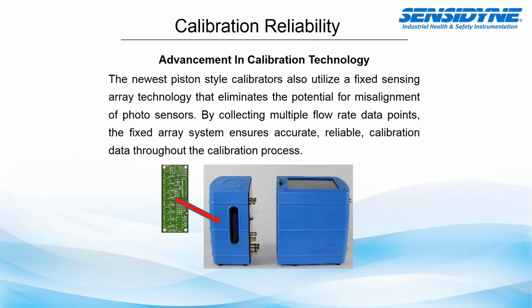Also, the Gilibrator 3, as shown in this picture here, uses a fixed sensing array technology. So what does this do? It eliminates the potential for misalignment of photosensors. As I mentioned earlier, some other dry cell calibrators will use optical sensors at the bottom and at the top of the cylinders. However, if these sensors become misaligned, your readings will be invalid, and usually they'll have to go back to the manufacturer or a repair center to be repaired.